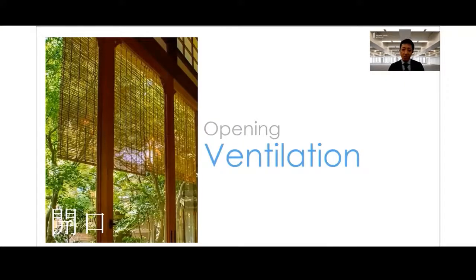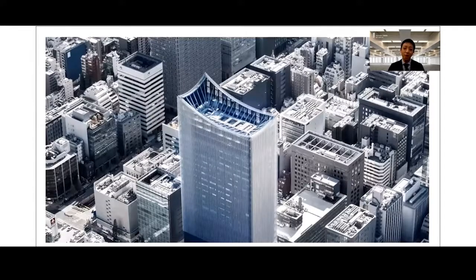Now I would like to move on to today's main topic, ventilation. For high-rise buildings, it is widely regarded as impossible to apply natural ventilation using wind pressure through the facade due to the difficulty of high pressure control. But this building challenged that with the development of a hybrid ventilation system and proved that it is very effective under local climate conditions in Tokyo. The natural ventilation system for our project uses both wind and stack pressure in a complementary fashion. The intent was to maximize the effective period and mitigate fluctuation caused by weather conditions for stabilized ventilation.